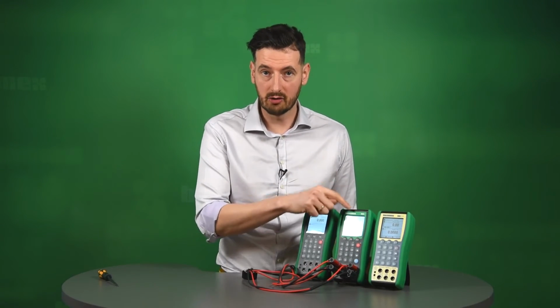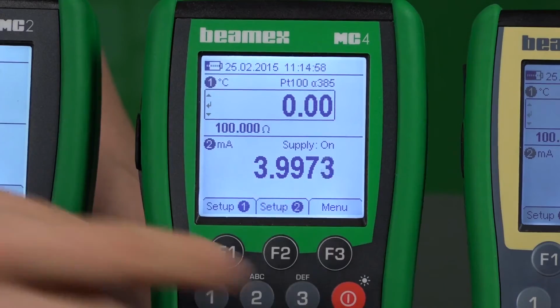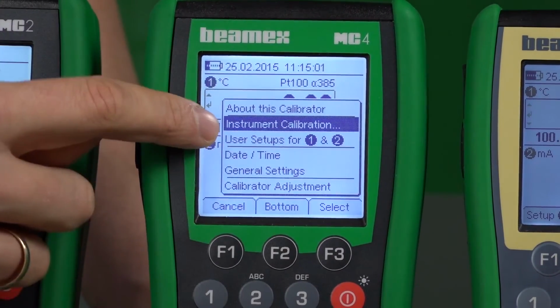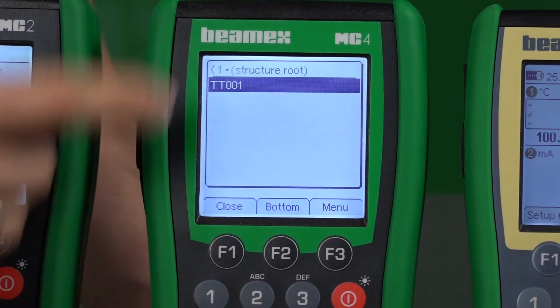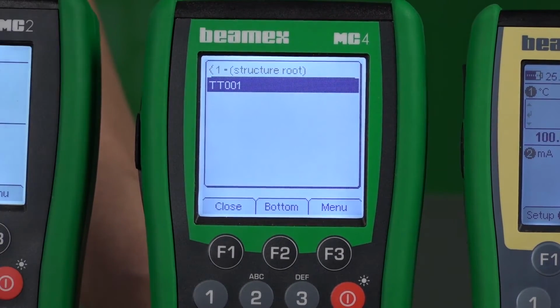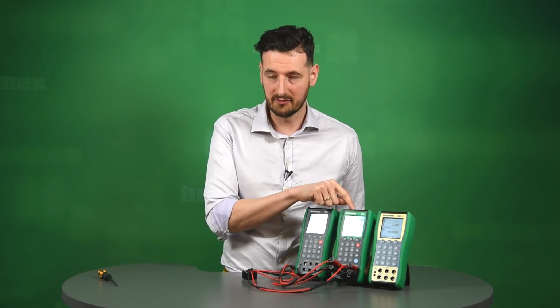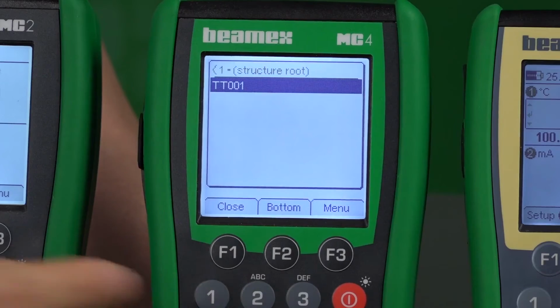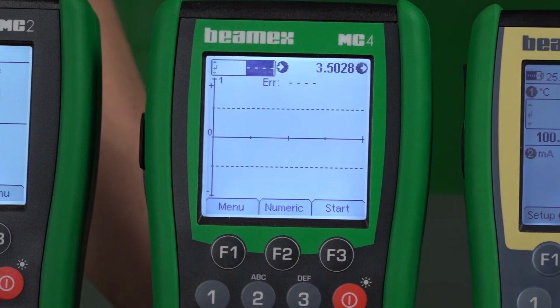Let me right now go to the documenting part of this calibrator and show how we can go through 5-step up and 5-step down. All we have to do right now is go to our documenting part on our MC4 and document the whole process. So we're going to do that. Now click menu, click instrument calibration. We also have one already saved in the memory of the MC4. What that means is basically we went to our CMX calibration management software, we sent the position from it to the MC4, and we're just going to access it right now and start the calibration. So let's do that now.